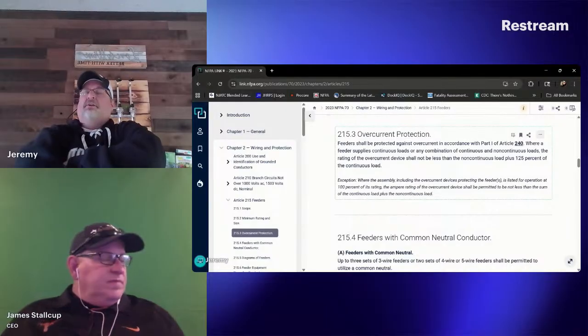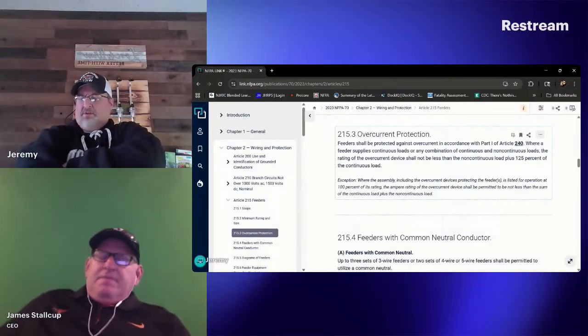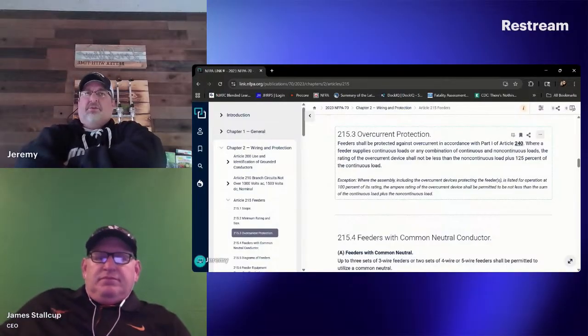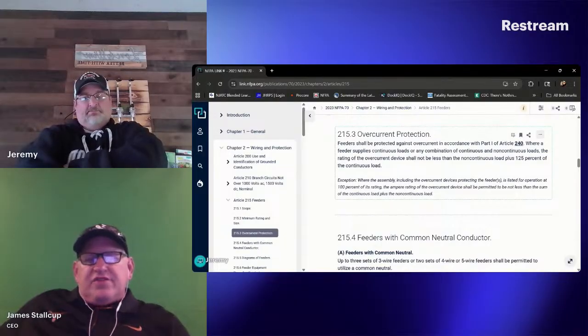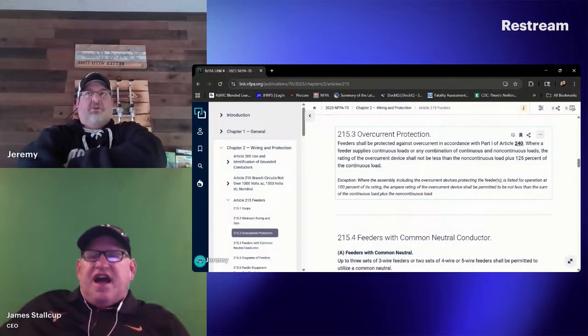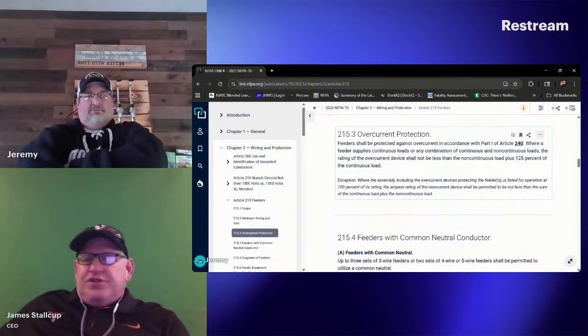All right. So your 724 amps of continuous load got us to 905? Yeah. I think it was. So why can't I use an 850 amp overcurrent device? Why can't I use an 825 or 863? What says I have to use a 900? A 900 amp is the next one below it. But where does it say you go to the next one below? It's not a standard size that's listed in table 240.6A, but you can go on any website, Google, whatever, and they have 900 amp available. That's where you're dropping down to the next size.